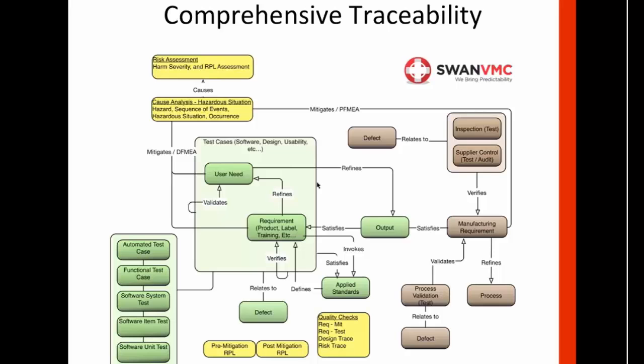So essentially that's the design piece, or the traceability. One of the reasons to separate these two work items is the user needs are validated, and we want to specifically have a list of validation tests, and then the requirements are verified. So in our procedures for listing out these two different things, they're in two different lists, and we have different tests to tie each one out. And then, of course, the output satisfies the design requirement, and that output is our specifications, essentially.